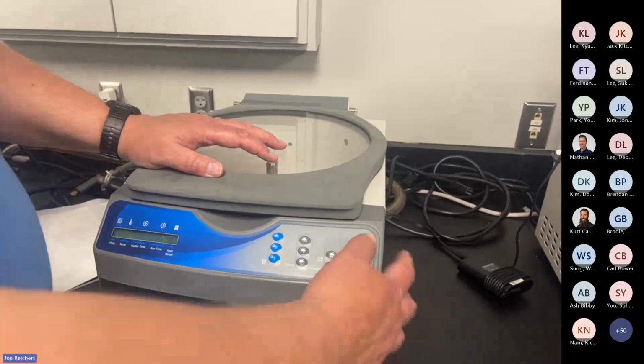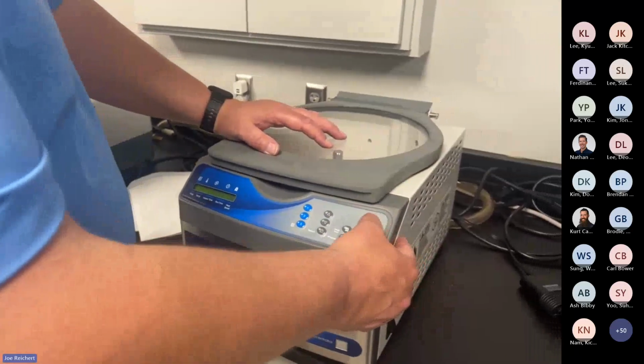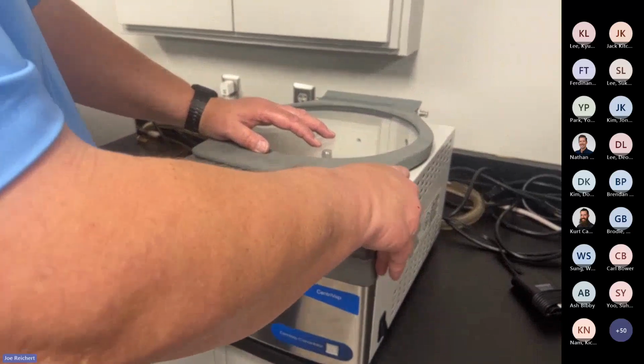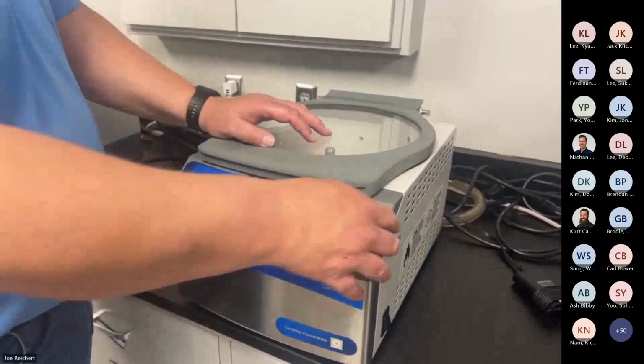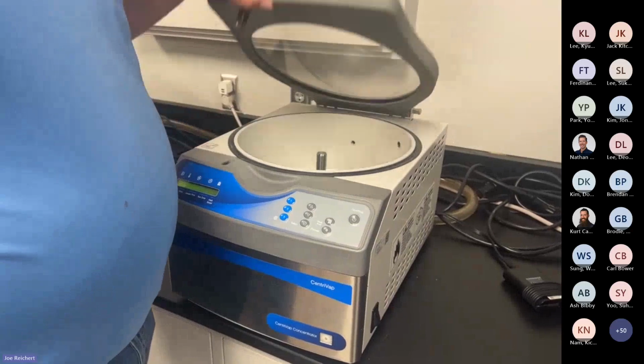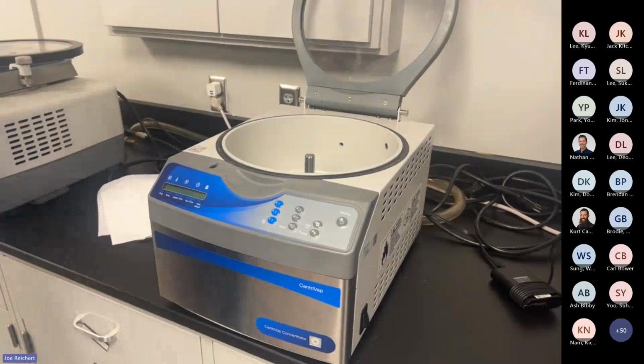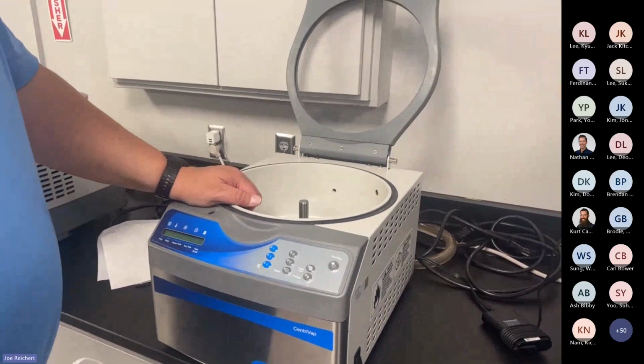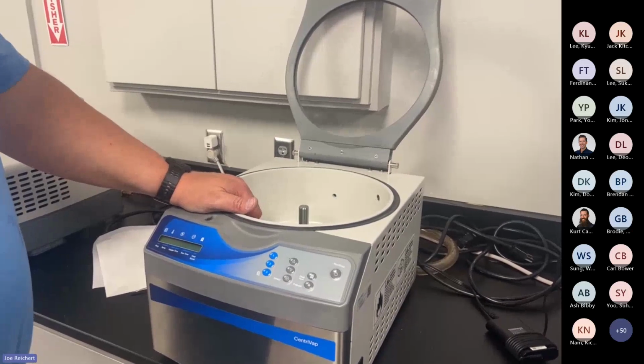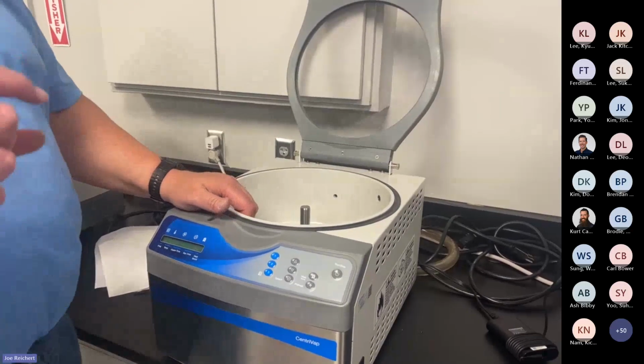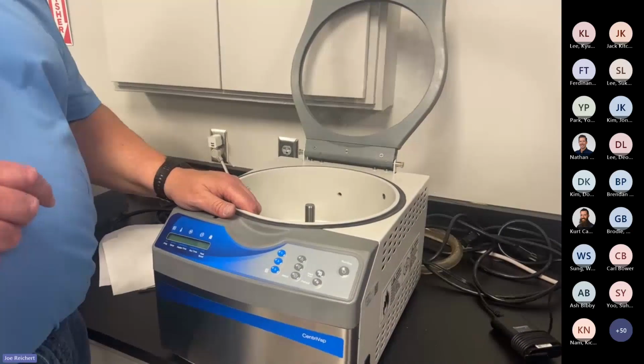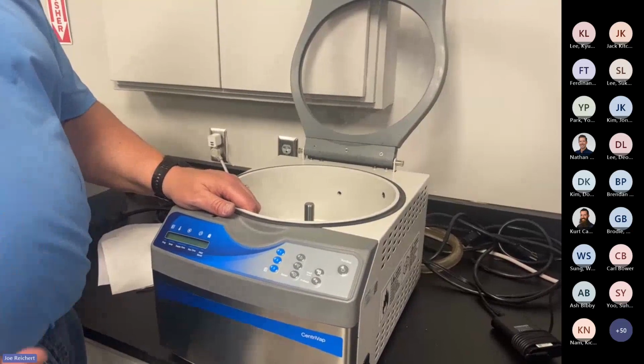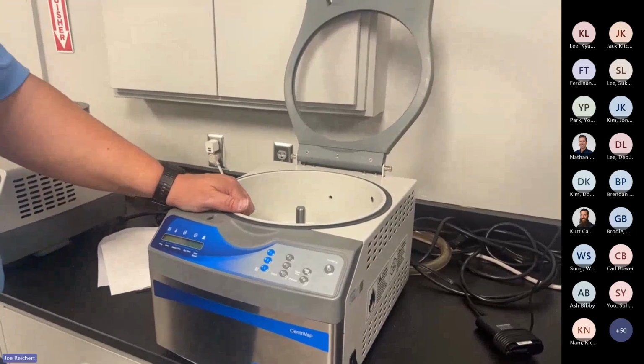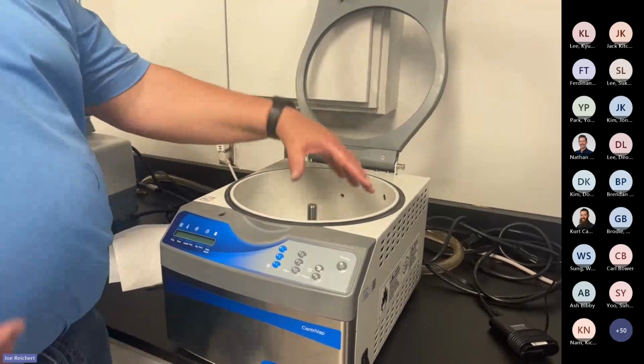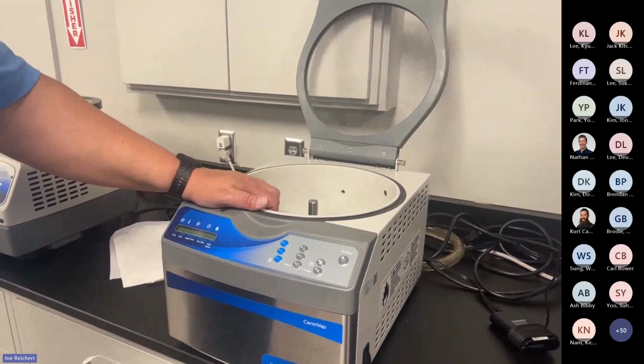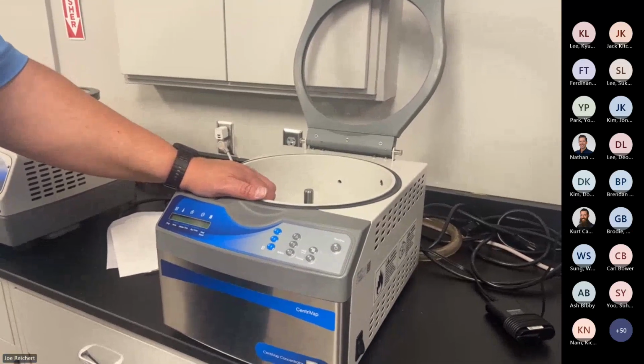We're not too concerned about the speed of the condenser or of the rotors, because that's only there to keep the samples within the tubes as it's spinning. And if you don't spin and you apply a vacuum, then you're going to boil those samples and take them out of the tubes. That's why we have the rotation. Something that has come up every once in a while on drying samples is when customers have an issue with microcentrifuge tubes. So if you had a rotor with microcentrifuge tubes, and for example, they had 10 samples in there, 4 of them dried, 6 didn't. Well, that's not really physically possible because they're in the same environment of a heated chamber, they're being applied by the same vacuum. So again, the CentriVap is doing its job because it's holding a temperature and it is holding a vacuum.